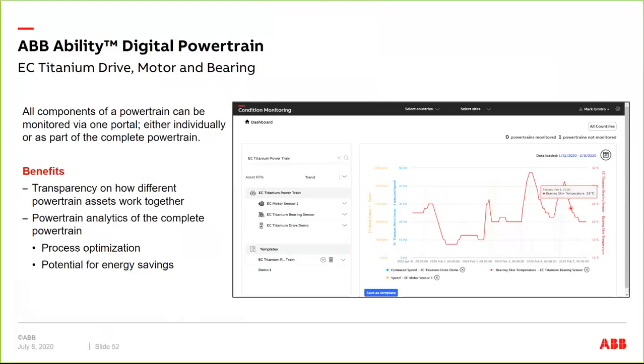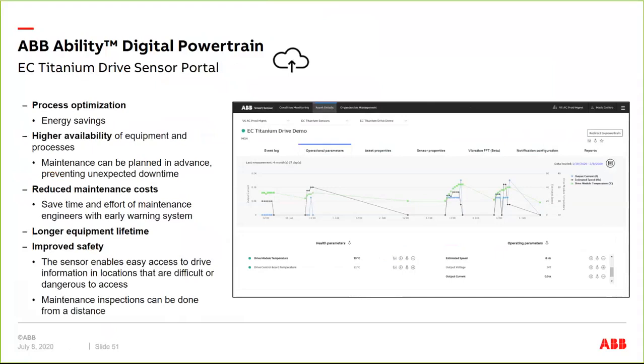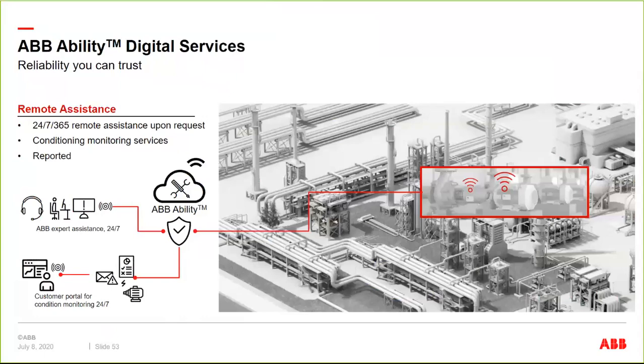So let's say you had a bearing sensor that was on a fan system. You might be looking at vibration or temperature of the bearing, and then you might want to correlate it against speed or power consumption of the drive. And so the digital powertrain takes multiple sensors and marries them together, and so you can look at multiple sensors in a system versus just the drive sensor itself. So again, it's a predictive and preventative maintenance tool.